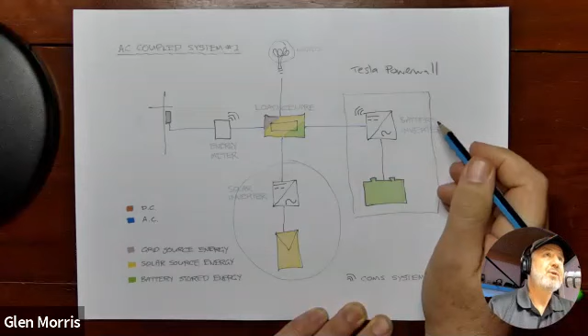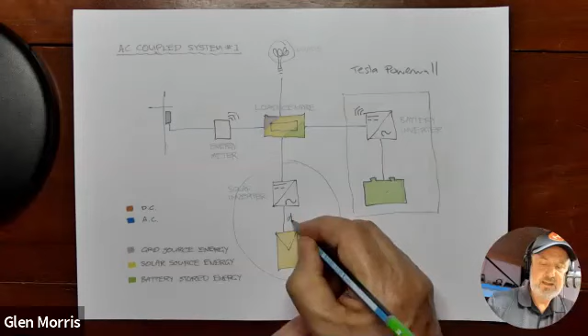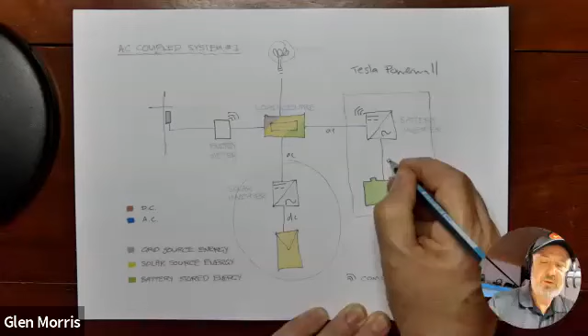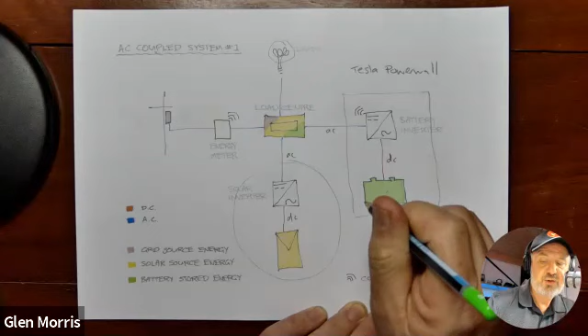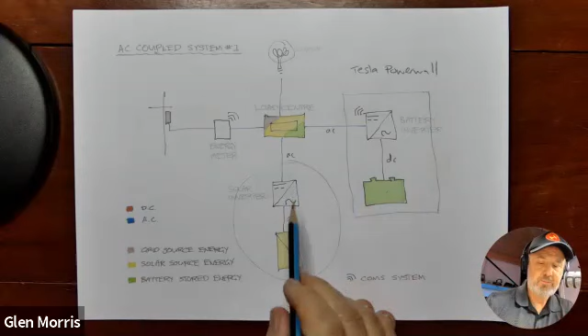It allows you to what's called AC couple. The word coupling refers to how the solar energy is transferred to the battery. It doesn't go through — well, this is the DC cable here, then it goes through an AC cable and gets converted back to DC. So the coupling between the solar generation and the storage is through the AC bus, which is why it's called AC coupling. The beauty of AC coupling is it doesn't matter what brand the solar inverter is.